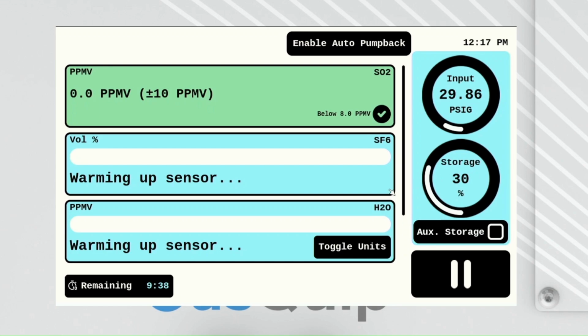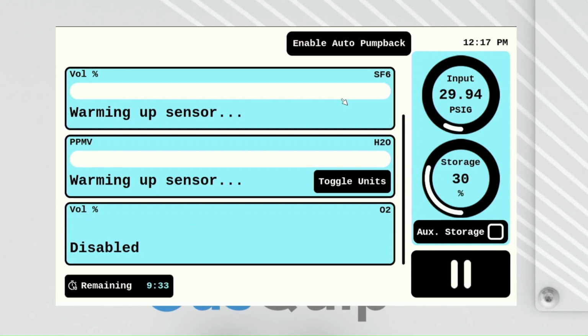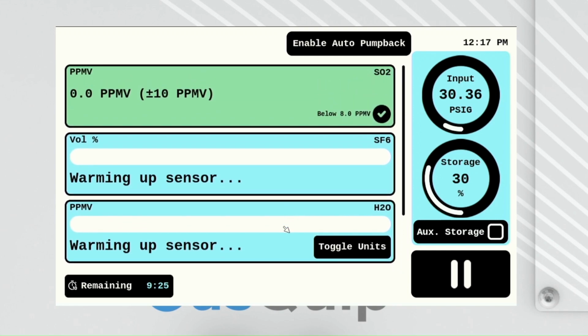If you have more than 3 modules installed, you'll have to click into this and scroll down. We can see that our O2 sensor module is disabled currently, so that'll just show disabled. And now we can let these SF6 and H2O modules warm up for this first test of the day.